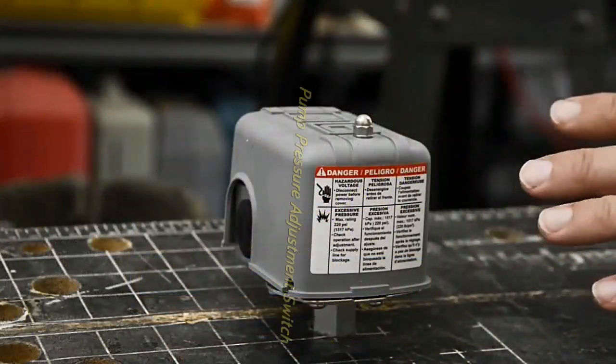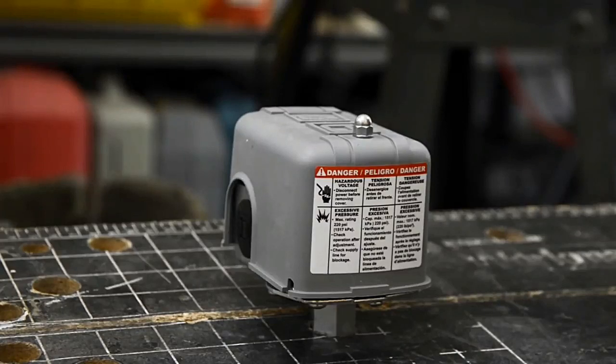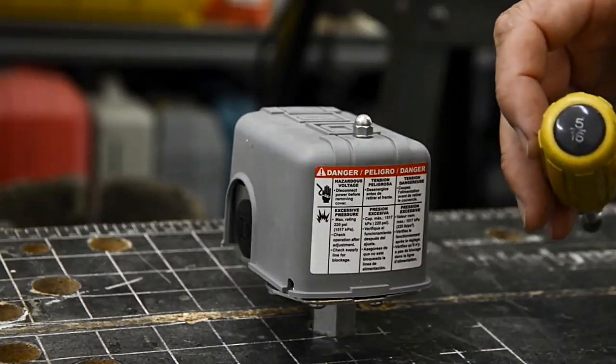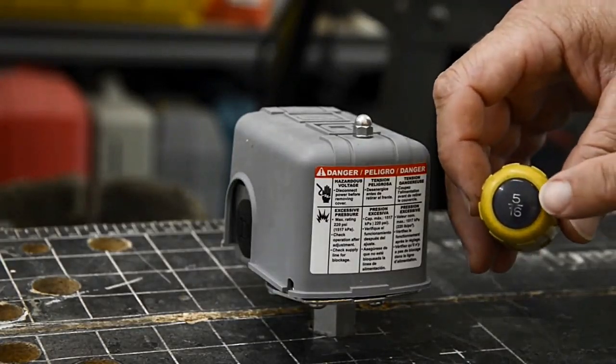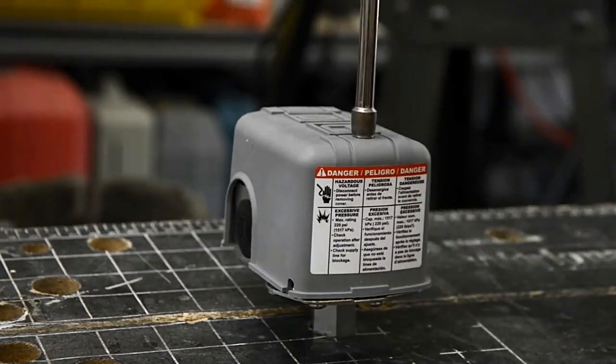We're going to adjust the Square D which is a standard pump control switch. It's also known as a pressure switch. We're going to take a 5/16ths, open up the top nut.